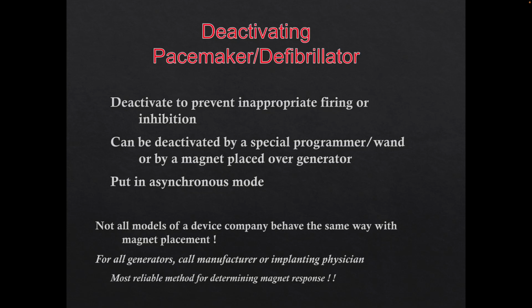All right. And once we use the magnet and take it off, does it reset? It reverts back. Yep. So if you have a defibrillator with a magnet on and then you remove it, it'll revert back and go back to shock therapy if it needs to, or anti-tachycardia pacing, however the settings are. If it's a pacemaker, the pacemaker never gets turned off. It's just that asynchronous mode, and then it goes back to whatever the original settings were on the device. All right.